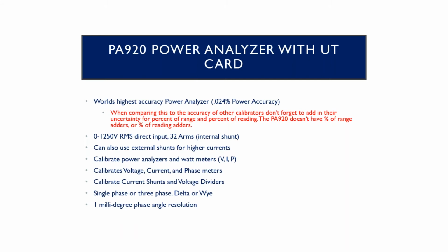Now we do have some other adders for things like voltage. If you start getting into the kilovolts, high kilovolts, there's a kilovolt square adder, and that's caused by the fact that that high voltage does a little bit of heating into the input impedance of the meter, and it warms it up just a little bit. So that's why there is a high voltage adder on there.